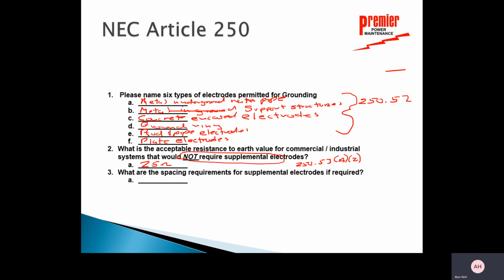What are the spacing requirements for supplemental electrodes if required? Good NETA question. So if my ground resistance test indicates that I need to have additional support electrodes, they have to be not less than 6 feet apart. So basically that means greater than or equal to 6 feet. And that's in Article 250.53, Section A as well. That's A3, if you're interested in that. So those are some typical type questions that you might get asked on Article 250.